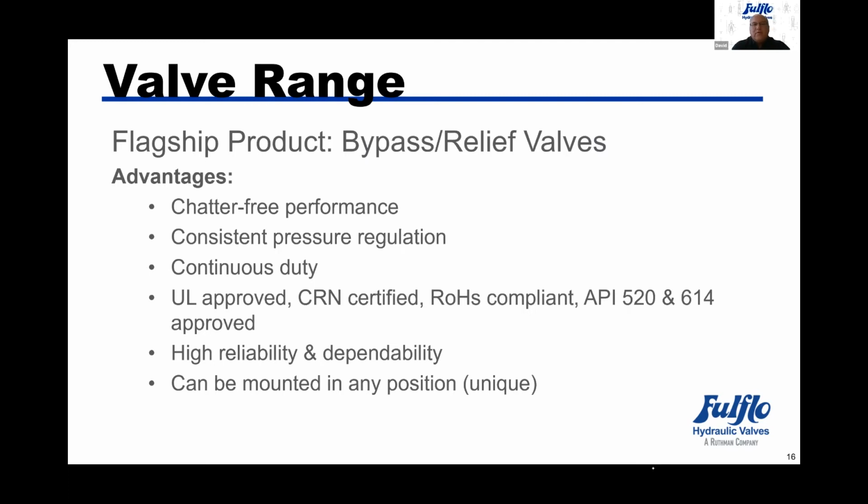We don't have a lot of returns when the valve is sized properly. You put the valve in the system and they tend to forget about it. So it's kind of a unique thing that Fulflo valves can work under those conditions. They can be mounted in any position. Again, that's unique to the valve industry. They can be shipped in any position, whereas most safety valves are shipped in the upright position.